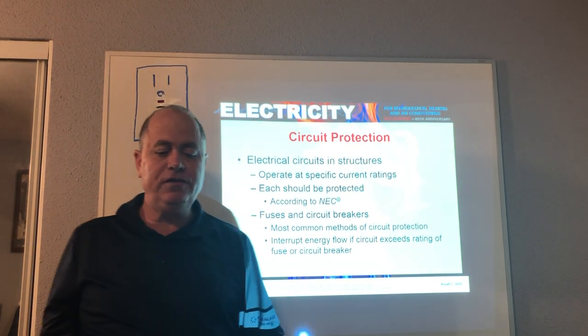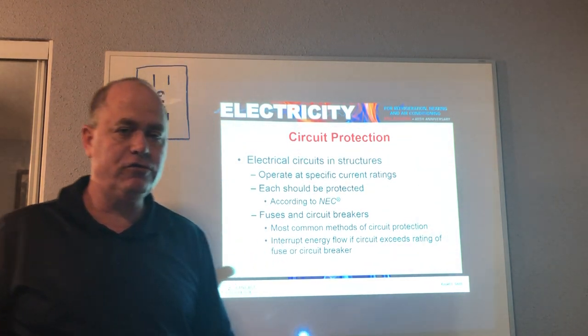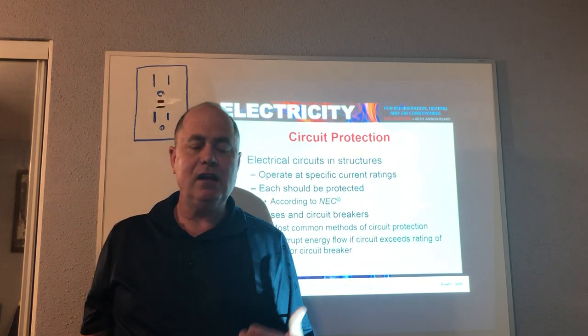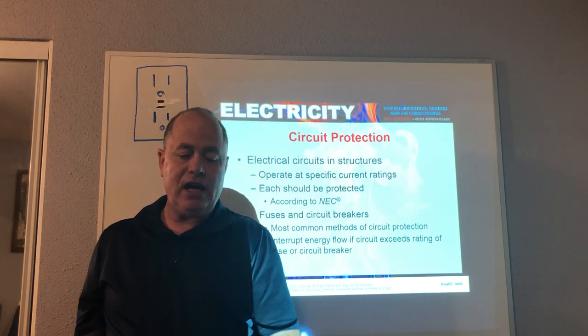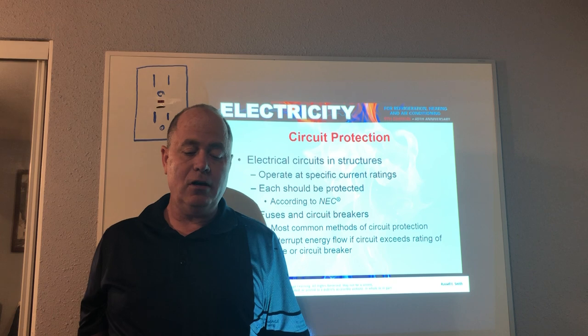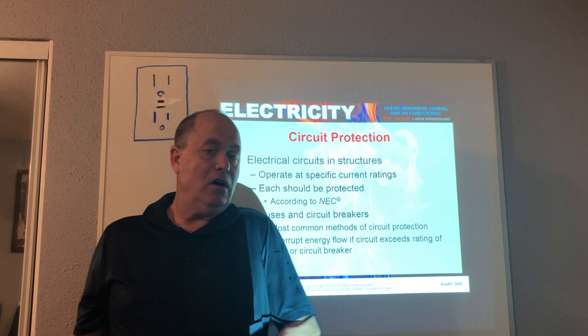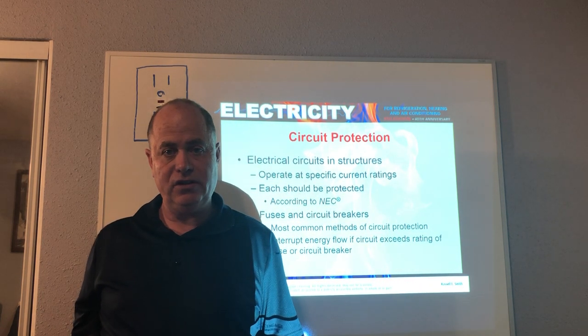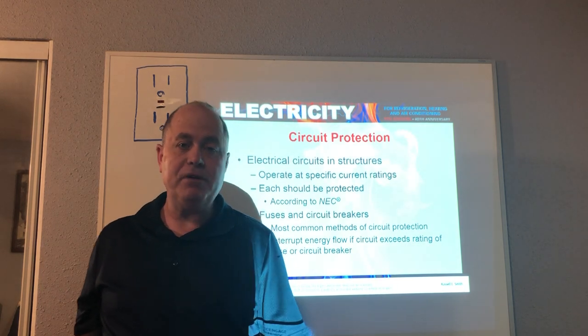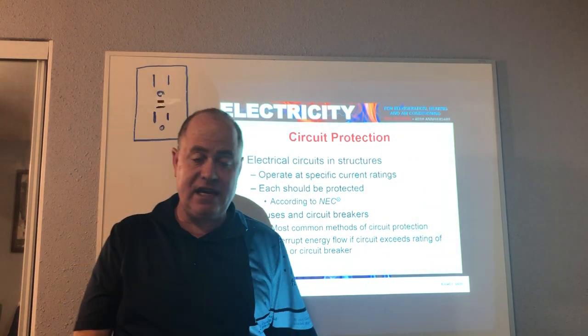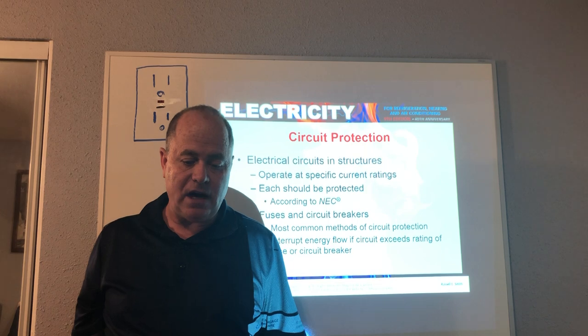Also, we use fuses in the air conditioning refrigeration industry. We should use dual element or time delay fuses and circuit breakers, which when you have an excess amount of current, it's going to trip it off before the wire would burn in half, again protecting against fire.